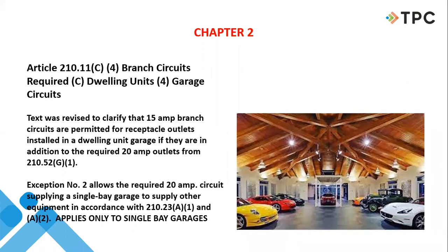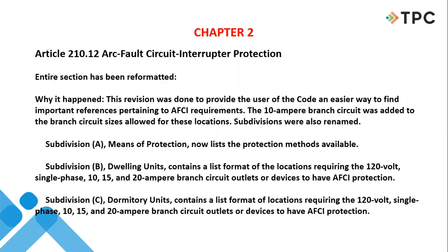I think it's just an area of concern where they're looking at what people are trying to do with these branch circuits based on their rating, and they're just being clear as to what can be fed from what and what rating of circuit is required in certain locations. The whole arc fault section has been reformatted. I'm not going to say that there's a whole boatload of new material here, but it's being presented in a more structured manner. It says here that the revision was done to provide the user an easier way to find important references. The 10 amp branch circuit was added to the branch circuit sizes that are allowed for these locations.